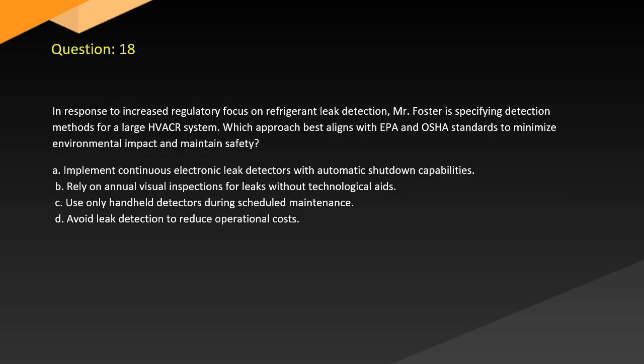Question 18. In response to increased regulatory focus on refrigerant leak detection, Mr. Foster is specifying detection methods for a large HVACR system. Which approach best aligns with EPA and OSHA standards to minimize environmental impact and maintain safety? A. Implement continuous electronic leak detectors with automatic shutdown capabilities. B. Rely on annual visual inspections for leaks without technological aids. C. Use only handheld detectors during scheduled maintenance. D. Avoid leak detection to reduce operational costs.